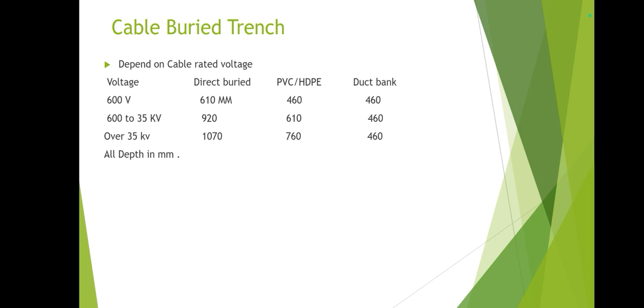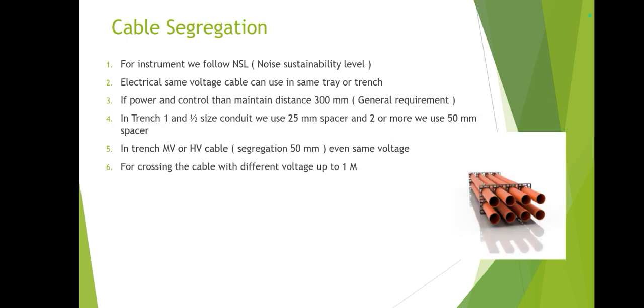The burial depth requirements are already discussed, but if you want to prepare your own notes, write down the required depth for low voltage, medium voltage, and high voltage cables. For cable segregation, instrument cables follow NSL (noise susceptibility level) — this is a large topic that will be covered in a separate video. For electrical, same-voltage cables can share the same cable tray; if power and control are combined, a minimum distance of 300 mm is required.